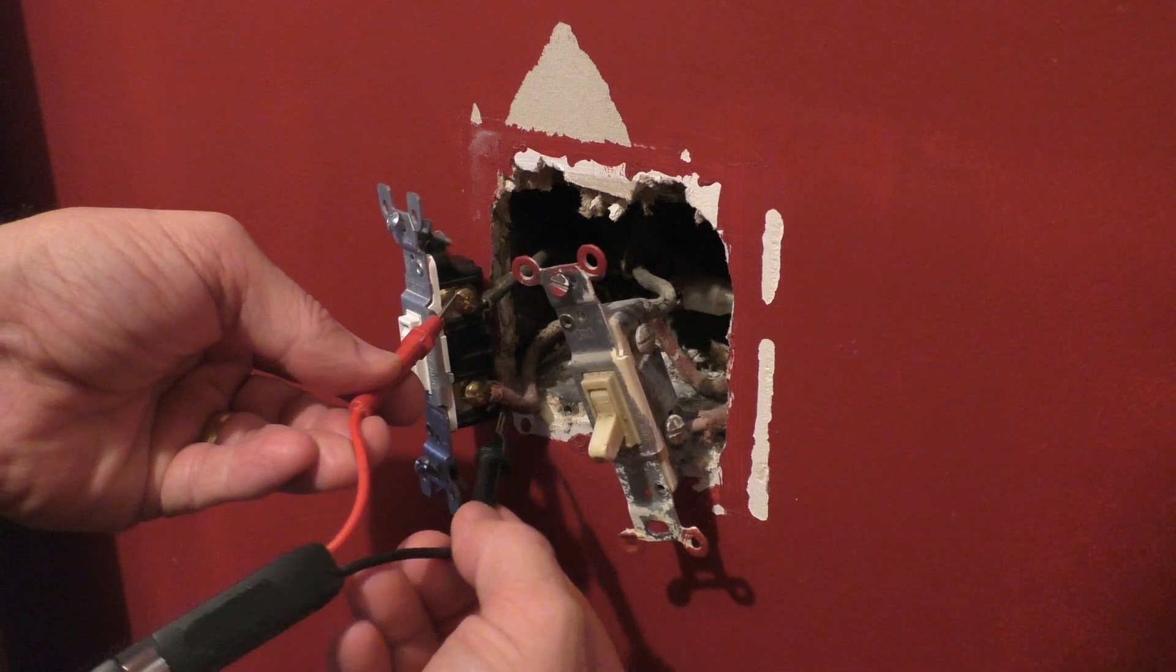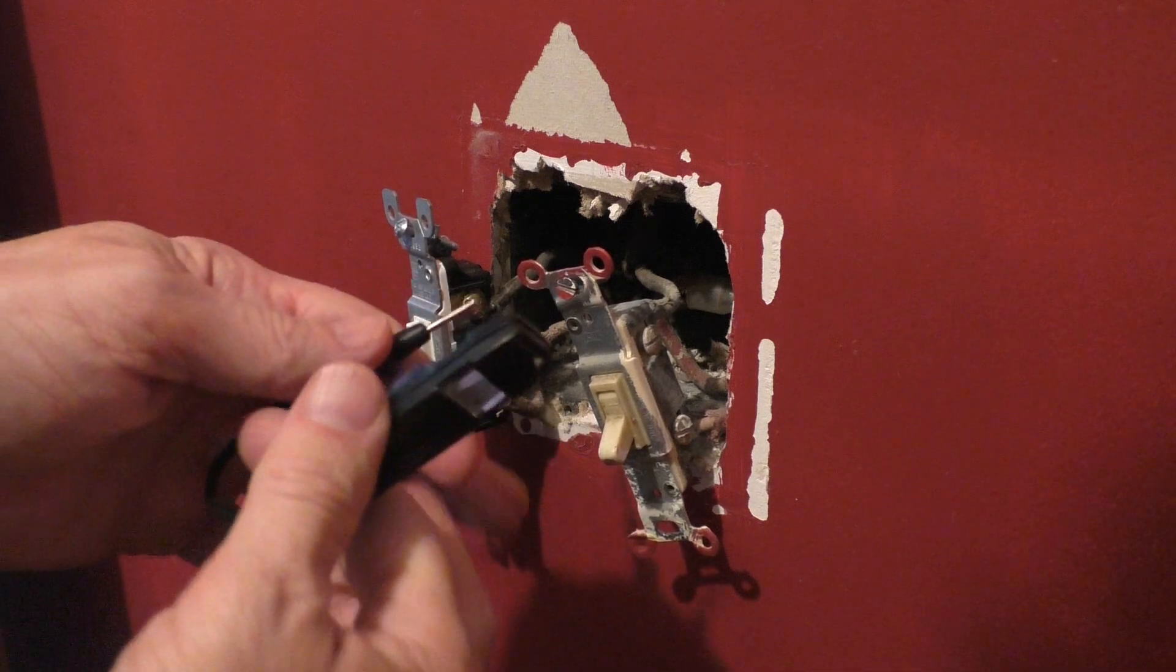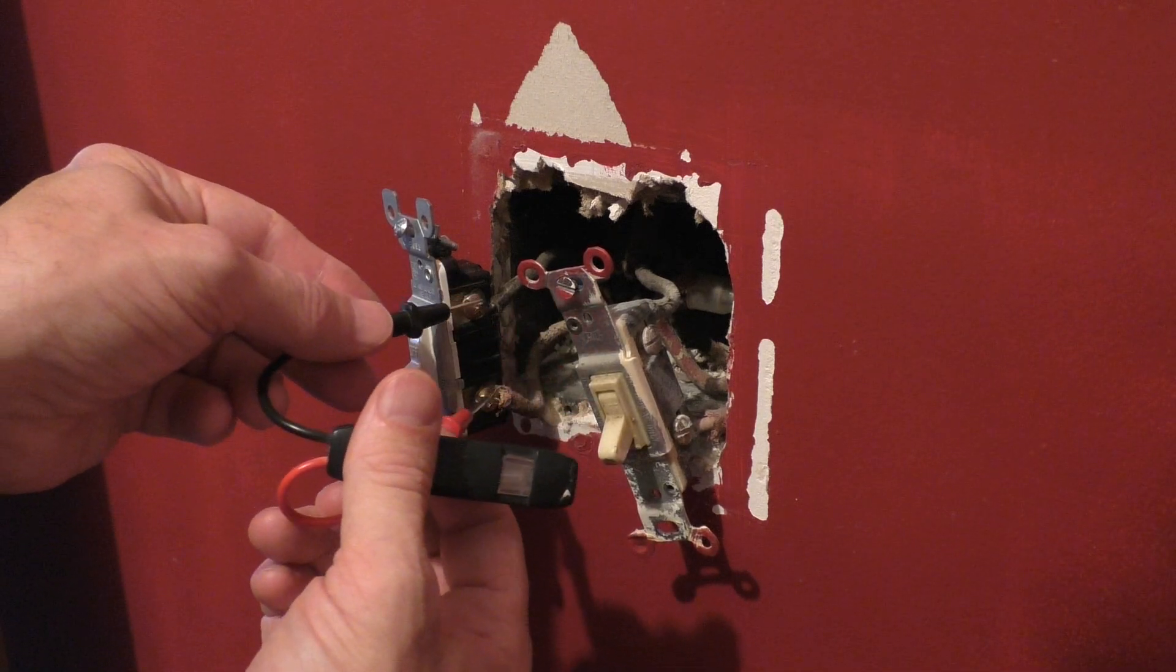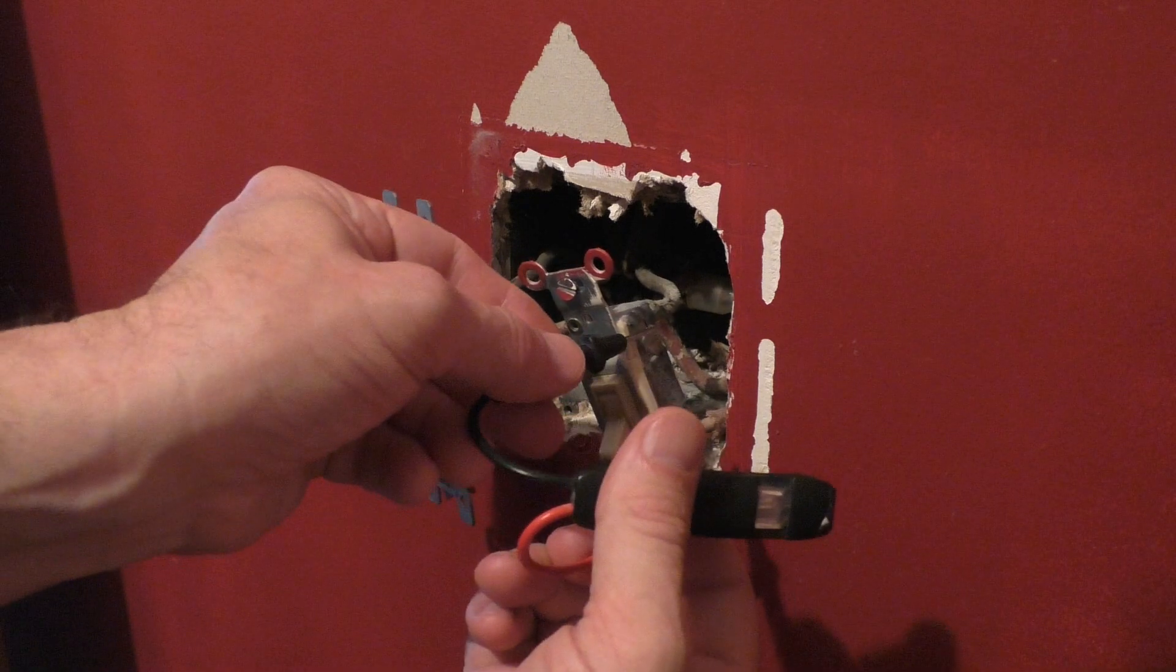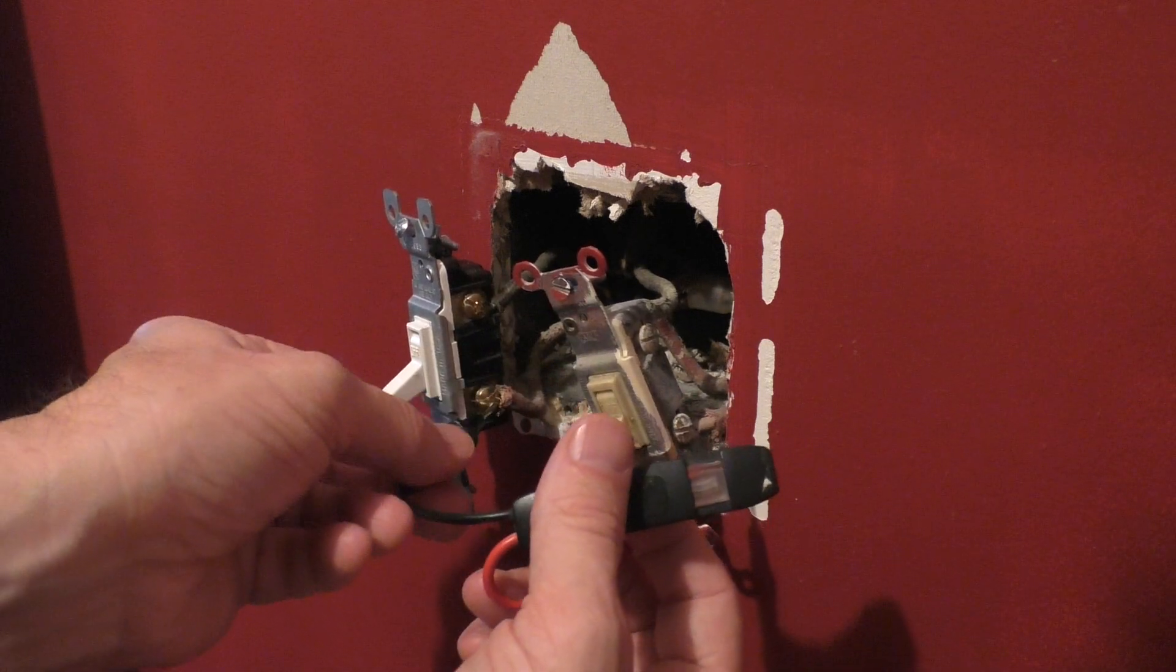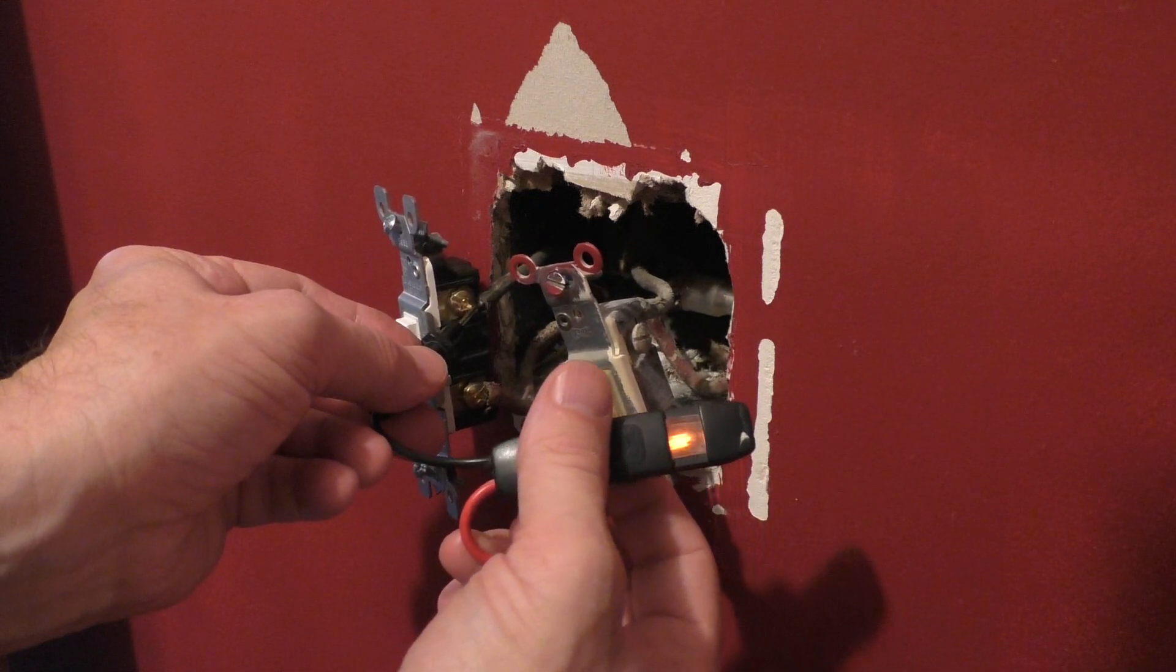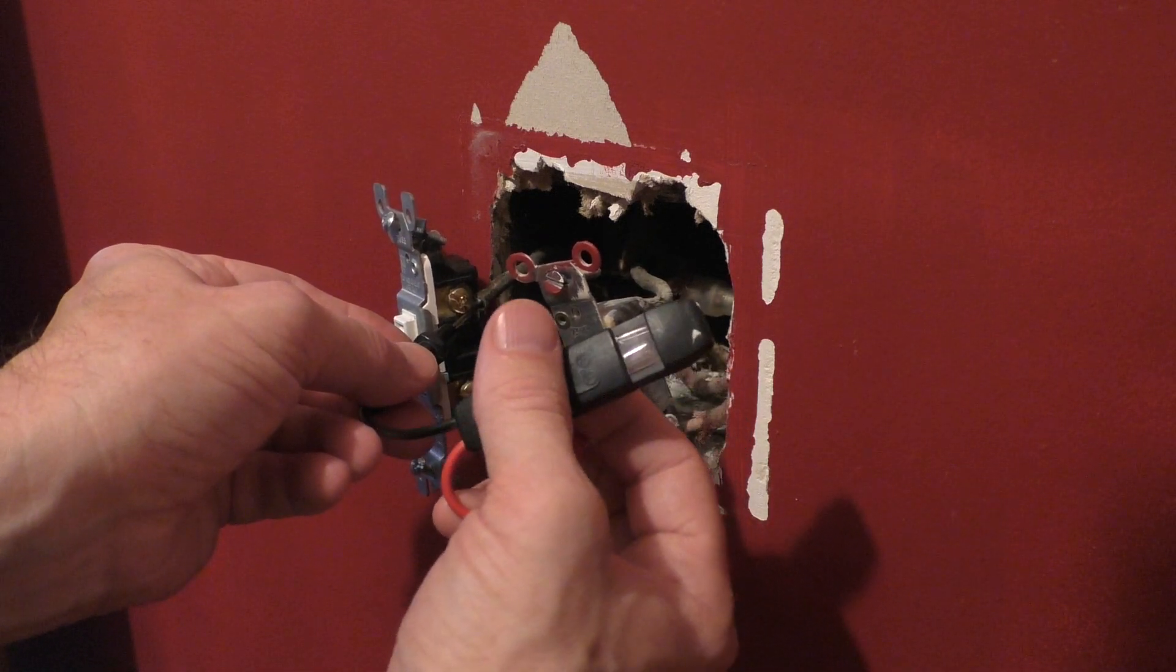Since this is very old wiring, I definitely want to verify which wire is hot. I have a pretty good idea based on how it's wired in the box, but I'm using my tester here just to go back and forth and verify which lugs are hot and which are not. It looks like the ones on the bottom are hot.